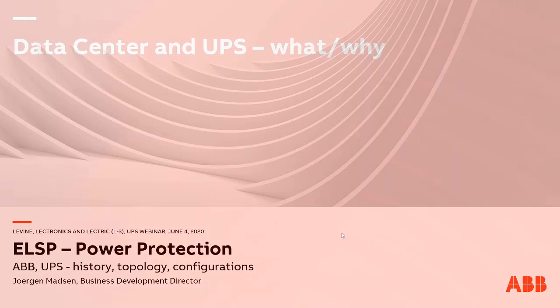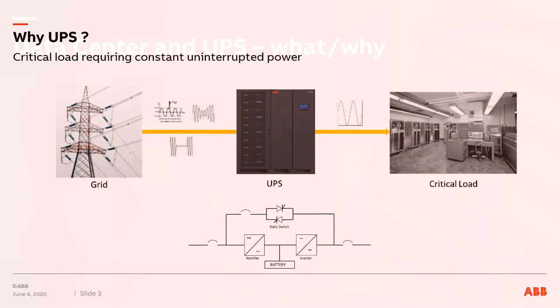So jumping into the presentation, like I said, the start is what and why. The reason for this slide is, if nothing else, I think 98% of UPS presentations out there have a very similar slide, or at least this is what the sales engineer would present to the customer. There's a critical load, it needs AC power, it gets that from the utility, but as we all know, it's not always clean, it's not always stable or uninterrupted. That's where the UPS comes in.